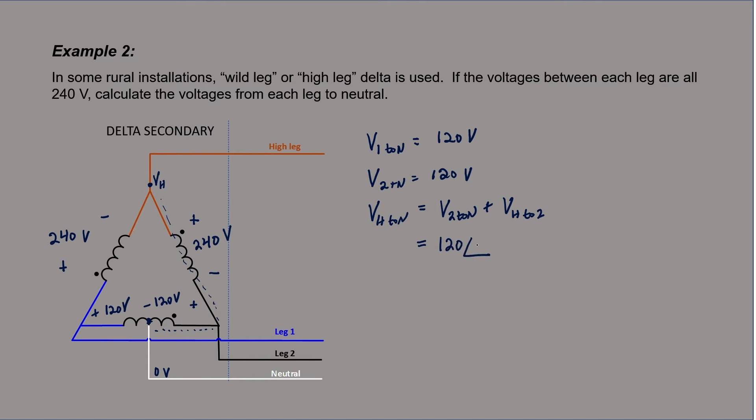Relative to our neutral point, leg two is 120 volts at an angle of zero degrees, and we know that our high leg is 120 degrees out of phase with the voltage at leg two. Remember that in a three-phase system, all of the phases are out of phase with one another by 120 degrees.